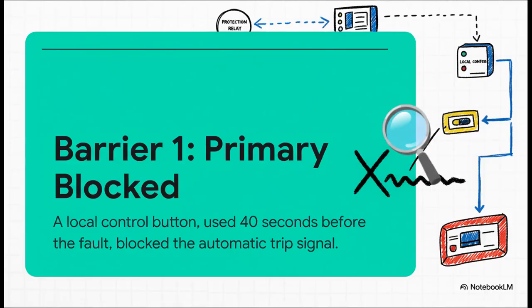And the timing here is just unbelievable. Technicians back in Lelystad were trying to figure out what was wrong with that faulty breaker. To do that, they switched a button to local control. This action, taken just 40 seconds before the short circuit, is designed to block all remote signals, and that included the automatic trip signal from the protection relay. So when the fault happened, the system correctly sent the command to open the breaker, but the signal was blocked at the very last step.